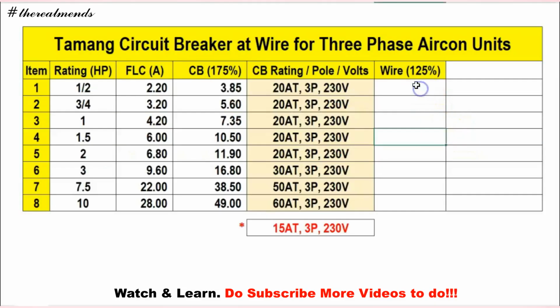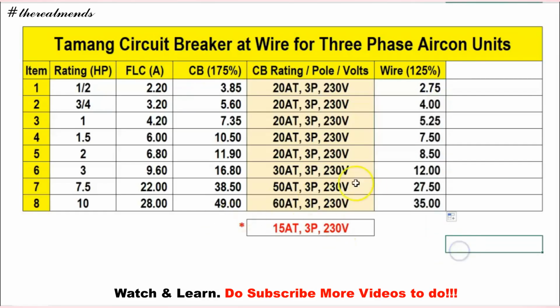Okay, so from the code, to size up yung ating wire, yung kanyang FLC, multiply natin siya ng 1.25. Okay, so sa 1/2 HP, meron tayong 2.75 amperes. So you can drag it para sa succeeding aircon unit natin. Okay, so for 3/4, meron tayong 4 amperes.